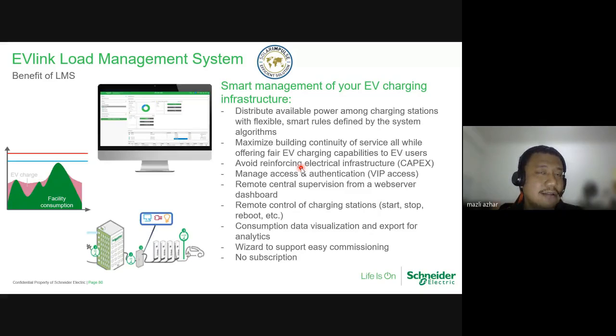to ensure that it will not exceed the subscription power, and all of the chargers will be maintained at the minimum level of requirement. So take for example, at night the power usage of the building is lesser. So it will provide more power to the EV charger instead of giving the power to the building itself. So this is how a load management system works.